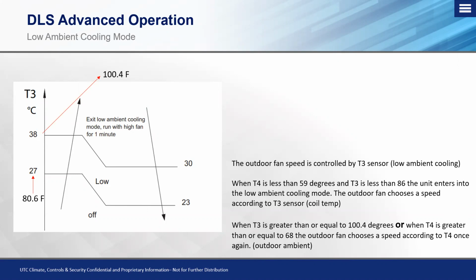So when that T3 sensor is greater than or equal to 100.4 degrees, or when the T4 sensor is greater than or equal to 68 degrees outdoor temperature, the fan speed goes back to being chosen by the T4 sensor. What we mean is, when that coil temperature is 100.4 degrees or the outdoor ambient temperature is 68 or above, it will choose fan speed by its default operation, which is the outdoor ambient temperature sensor, and take itself out of the low ambient cooling mode. You will see on the display that the system is in low ambient cooling mode. Again, that is to control the head pressure, and it's also what enables us to operate cooling mode in low ambient conditions, typically for server room applications, where we see it most.